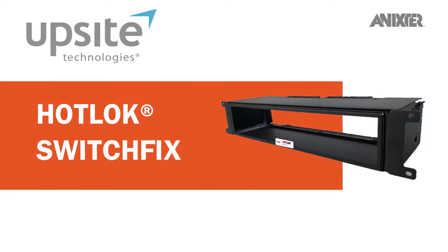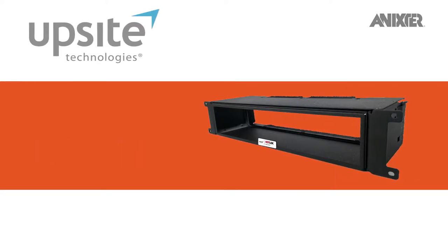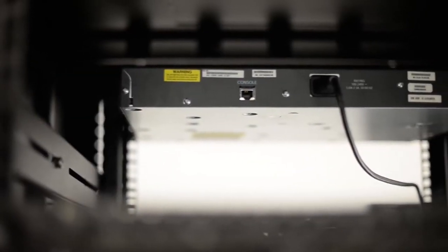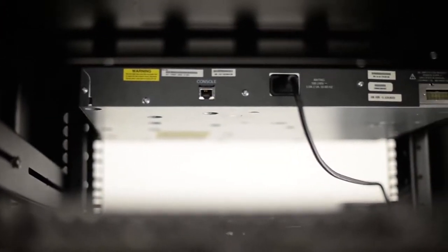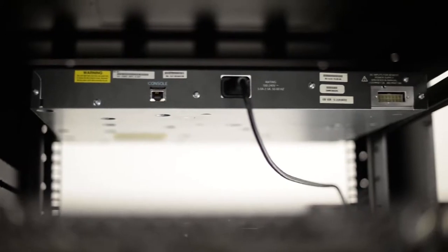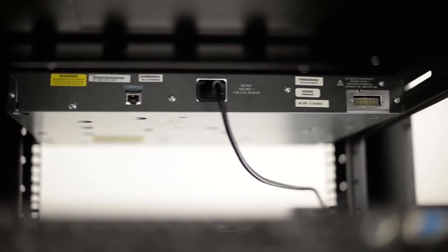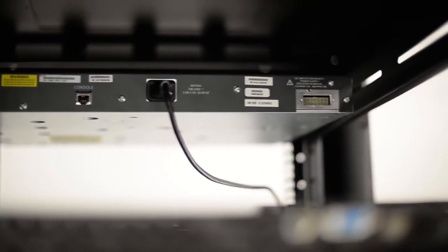Today, network switch equipment typically sits at the top and back portion of the server rack. This placement makes it difficult for cold air from the cold aisle to travel from the front of the rack to the intake sides of the network switch.